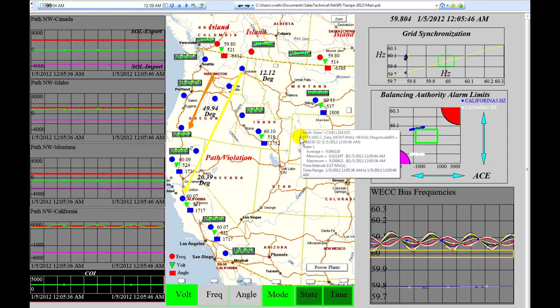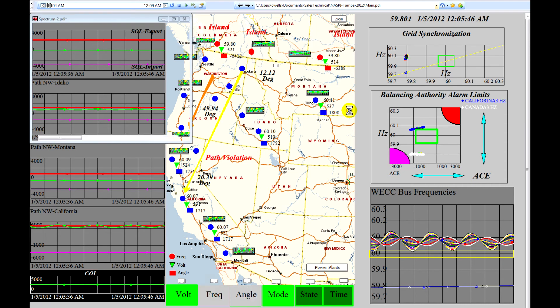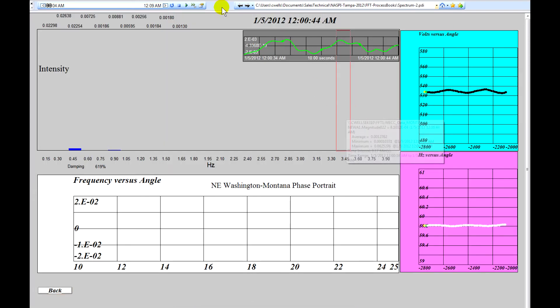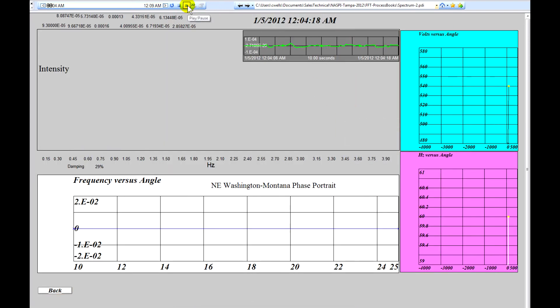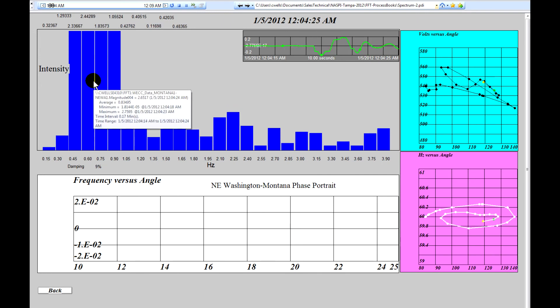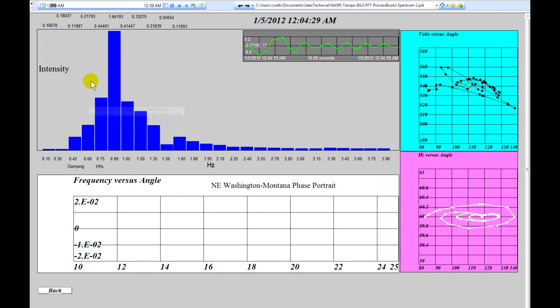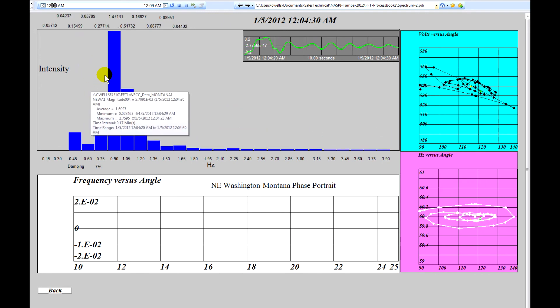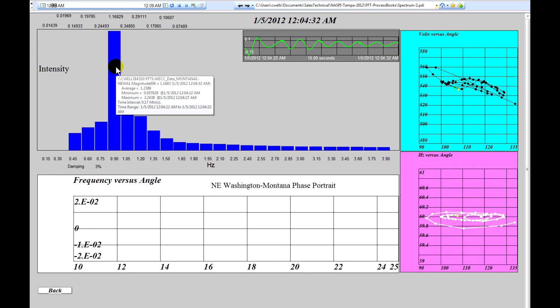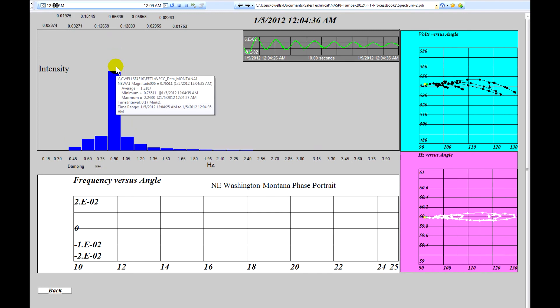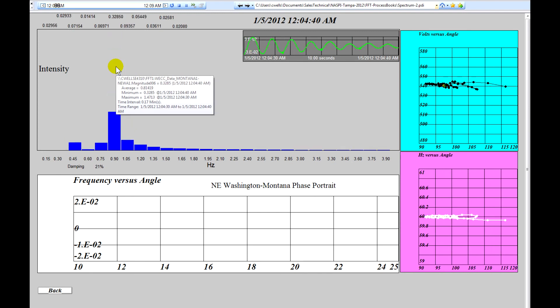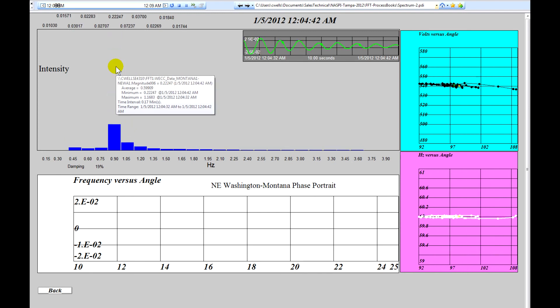Now the final thing we'll show is we'll look into more details on the oscillations and we'll play this. And you'll see that we see the initial disturbance, a substantial amount of oscillations occurring, and the oscillation mode is about 0.9 hertz. However, it's dying out very rapidly.